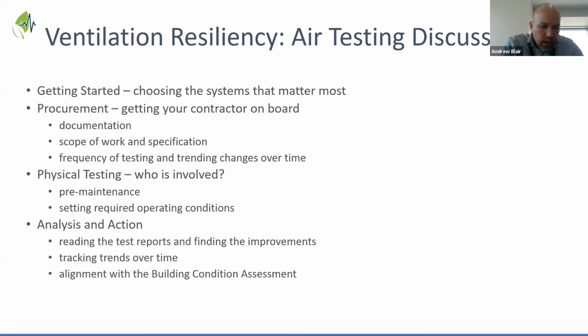One was for air and water balancing, to have somebody on my team that I could work with on creating the annual and the monthly reports that I wanted. Also, as you saw, you're looking at BAS graphics, and ensuring that what you're looking at on the screen is indicative of the actual physical systems and how they're operating is key. You're never going to win if those systems aren't reading the right information. So make sure you have a robust BAS contract in place, you create that partnership, and you invest in the constant maintenance of those systems. You're unforgiving on question marks on the system. It must be solved. It must be replaced, so that you can continue to optimize and create efficiencies.